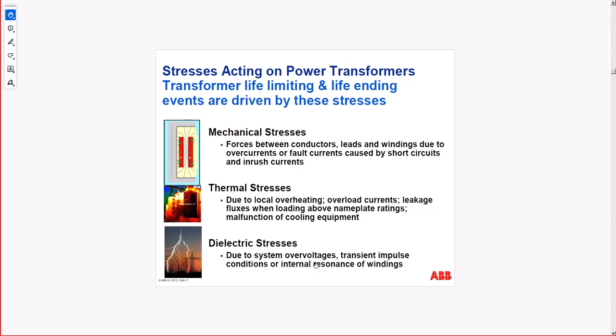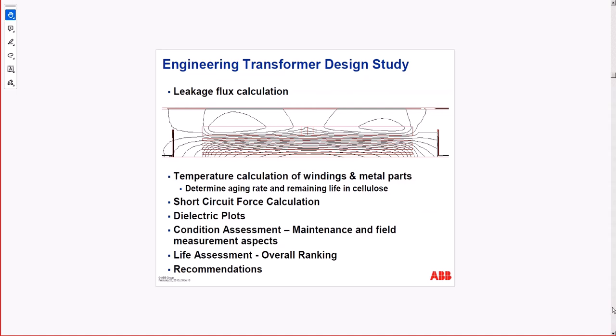Dielectric stress, any over voltages. So over voltage coming from discharge, like you can have natural discharge, or over voltage from switching, like Hydro One will switch the transformers for paralleling and giving backup transformers for the load. Those create high voltage switching, like capacitor banks for power factor and voltage correction. Even tap changers can give you over voltages. So anything like that may create a voltage stress in the dielectric. Okay, so those are the stressors.